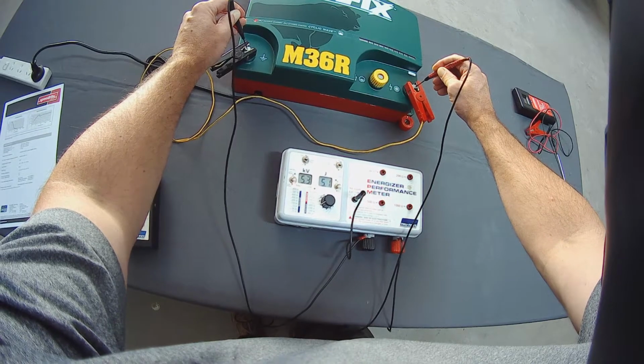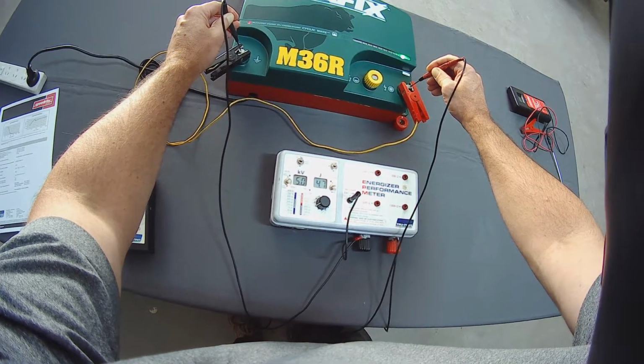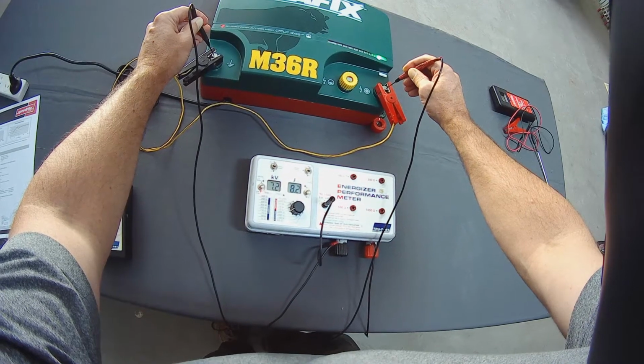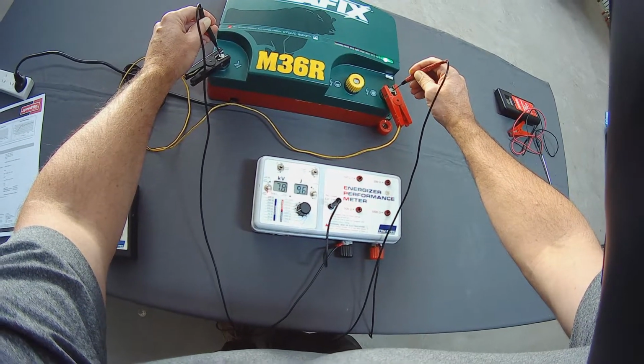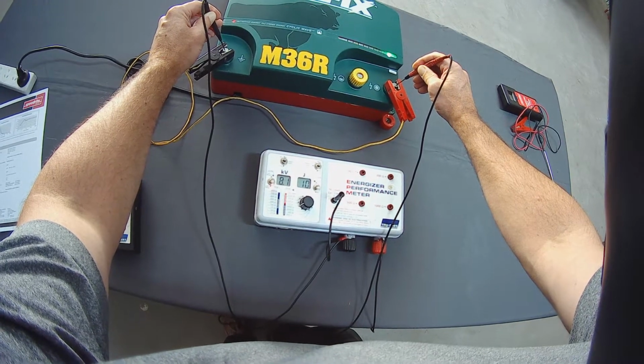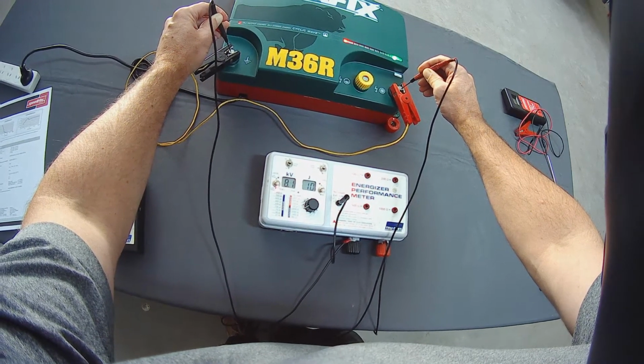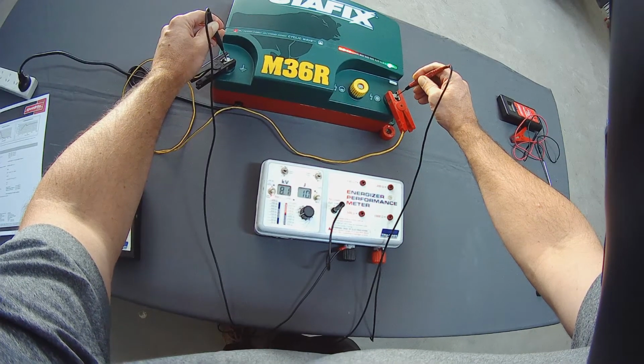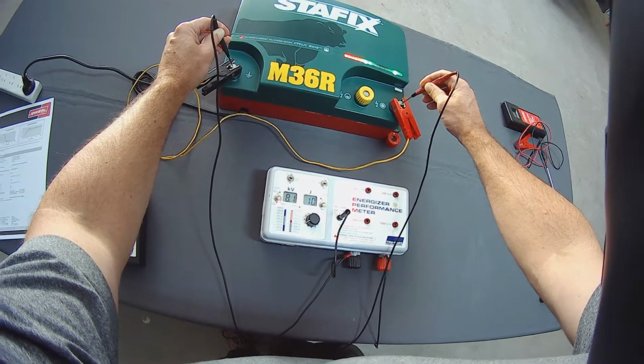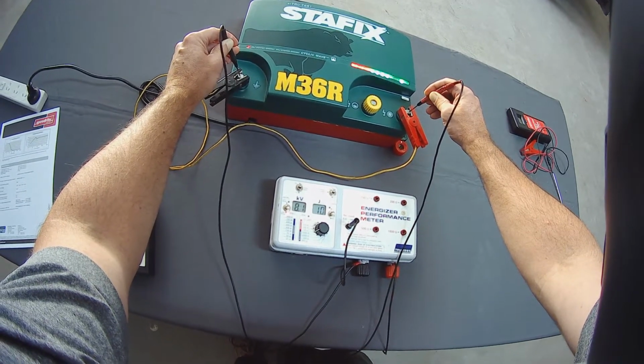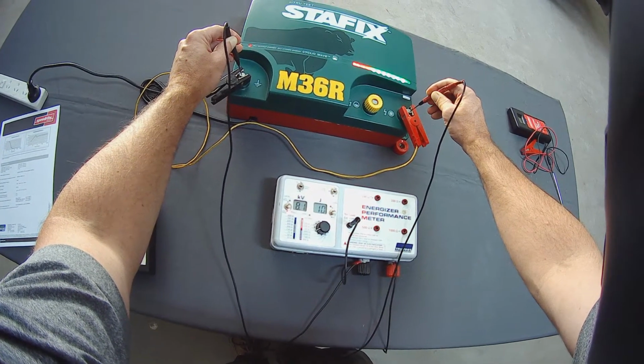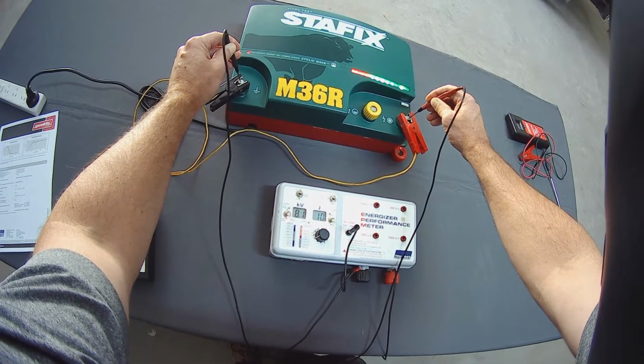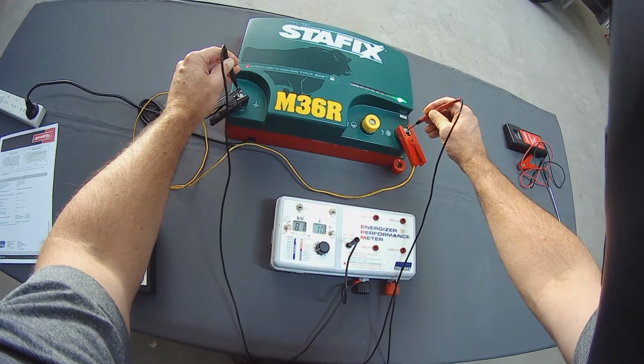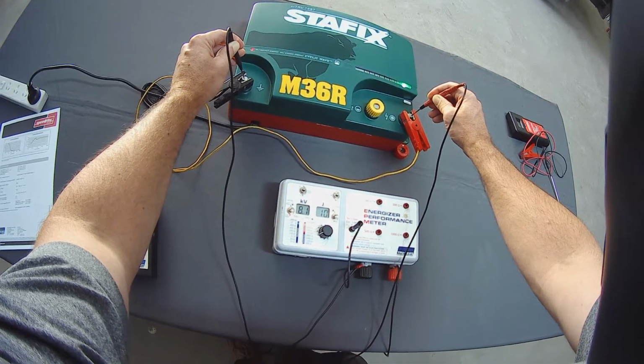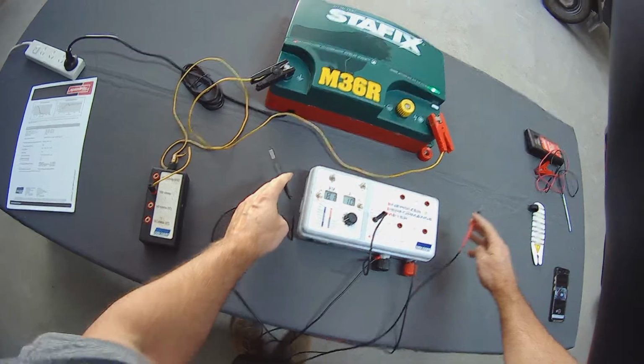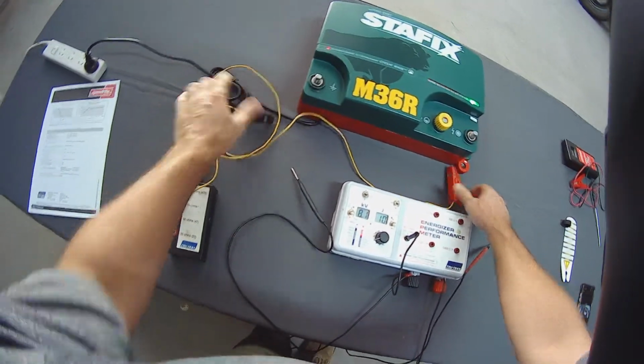What we should see is this Energiser switch gears. There we go. Our end light on our pulse bar has come on. Our joule rating has gone up to 10. We're 8.1 kilovolts. So what that means is this Energiser is working as hard as it can to maintain that 8,000 volts. So if we were to add even more load, we'd just see the voltage start to drop now. You don't want to leave that load on there for too long because these load boxes can get hot and burn out.